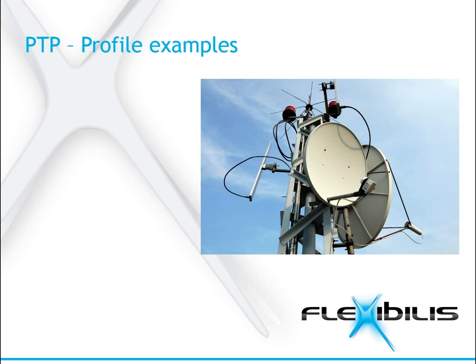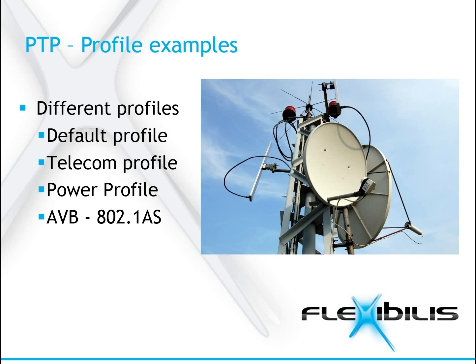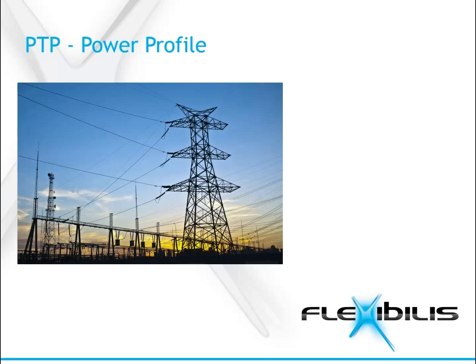Here are examples of different profiles. Note that there are more profiles than just the ones presented here. The default profile is currently the most commonly used one and uses UDP multicast. The telecom profile is used in telecom networks and uses UDP unicast. The power profile is meant for power system applications, and the AVB profile is for audio-video broadcast networks. FRS is able to support any profile currently defined. Next, we will look more closely at the power profile, since it is the profile most commonly used with FRS.